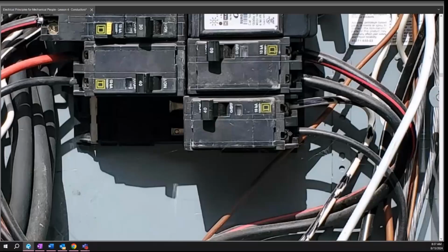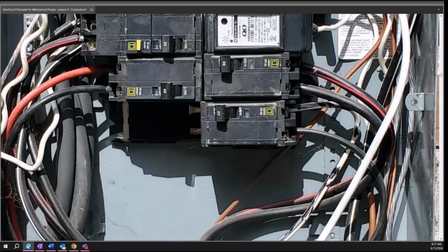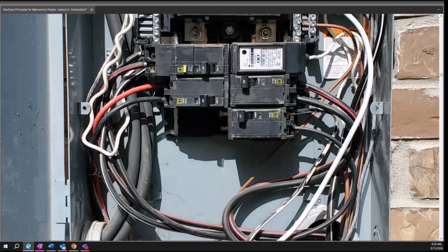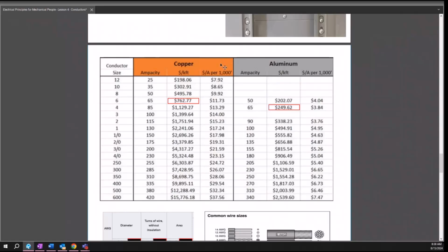Every 5 years or so, you come back and re-torque these terminals. Make sure they're still torqued down, because over time that expansion and contraction will work that terminal screw loose. So you can actually have a loose connection, which also increases heat. Those are two of the main concerns you have with aluminum. So, copper and aluminum. And all right, let's look at conductor sizing.